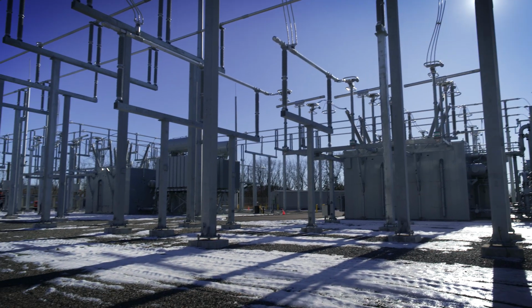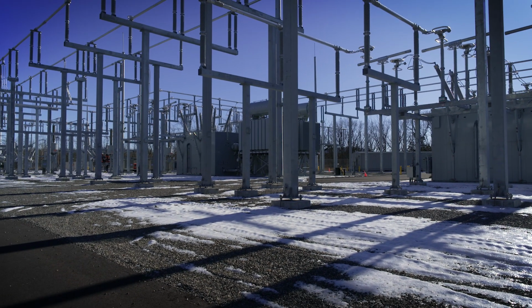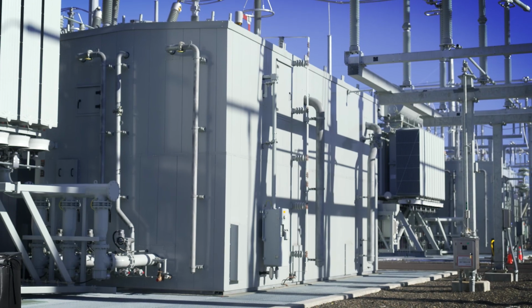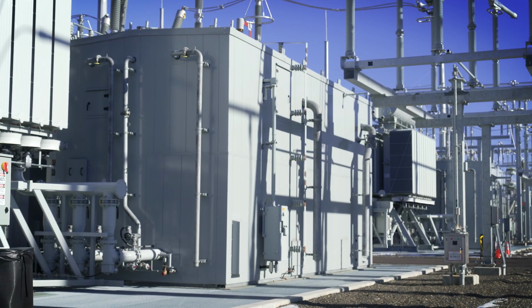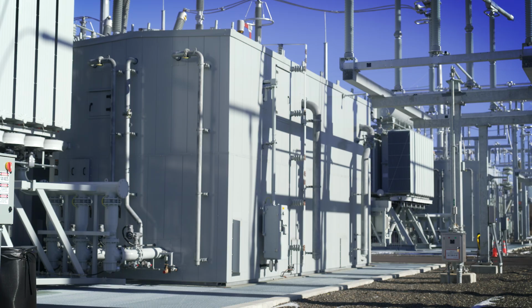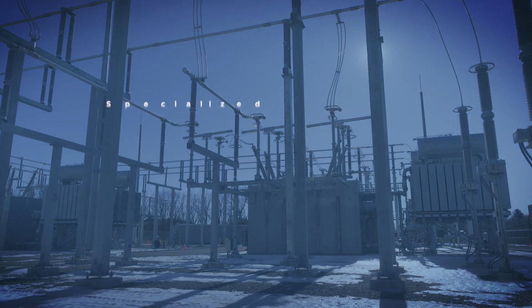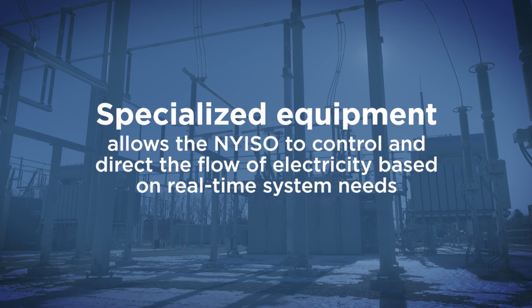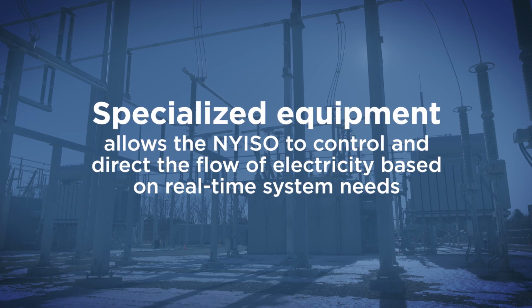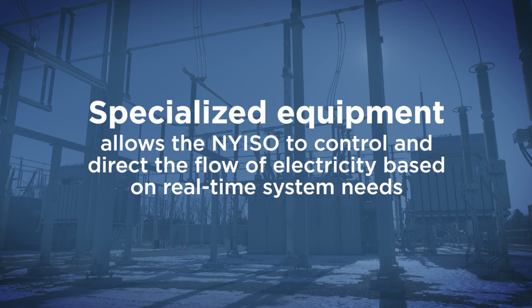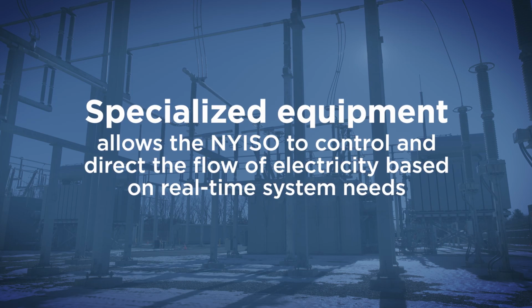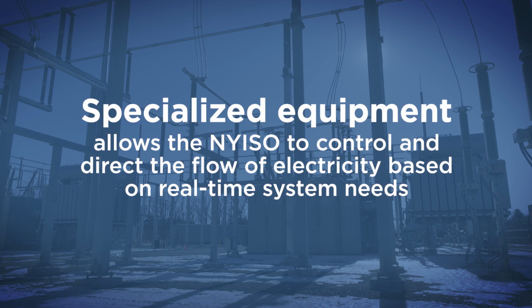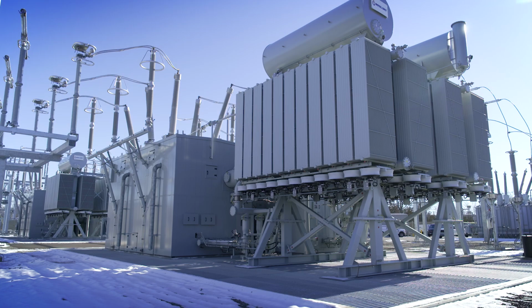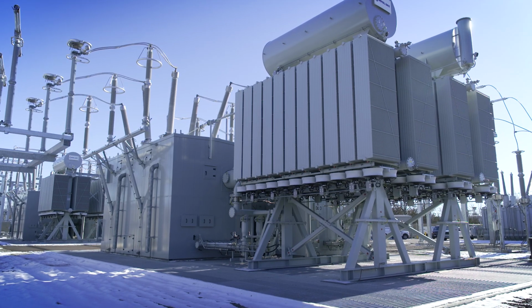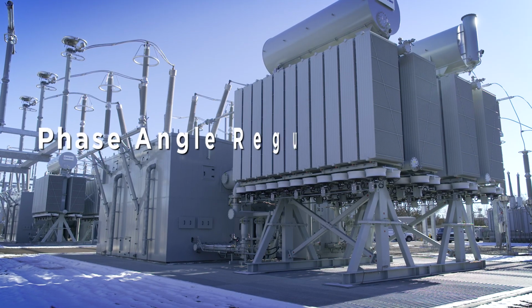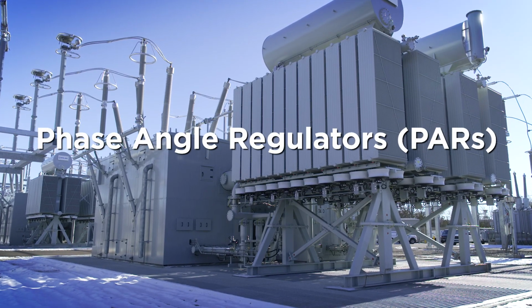While a substation's typical function is to connect transmission lines and control or change voltage, Dover Station is not just any substation. This station features specialized equipment that allows the manager of the state's electric grid, the New York Independent System Operator, to remotely control and direct the flow of electricity on the connected high-voltage lines based on real-time system needs. The key components behind this advanced capability are specialized transformers called phase angle regulators, or PARs.